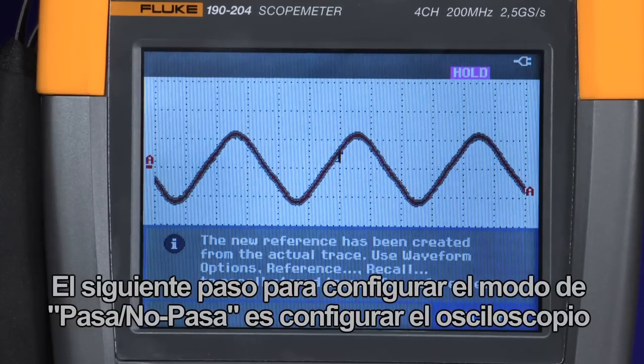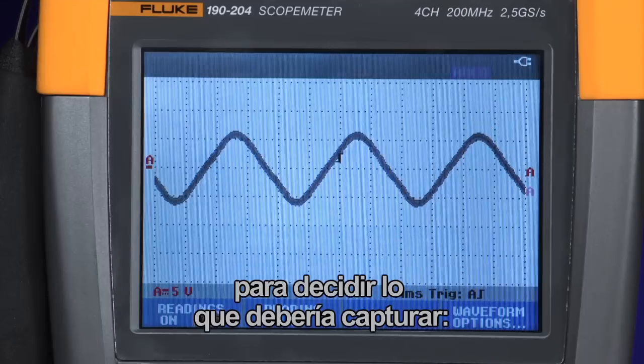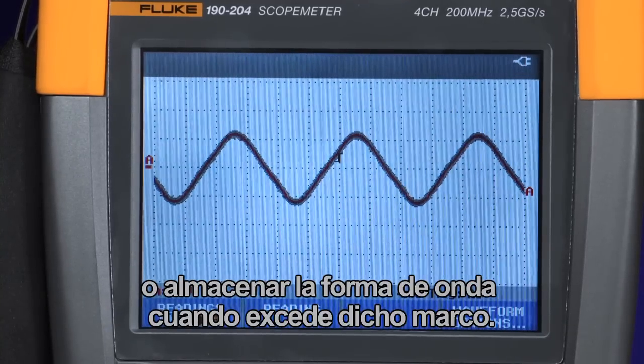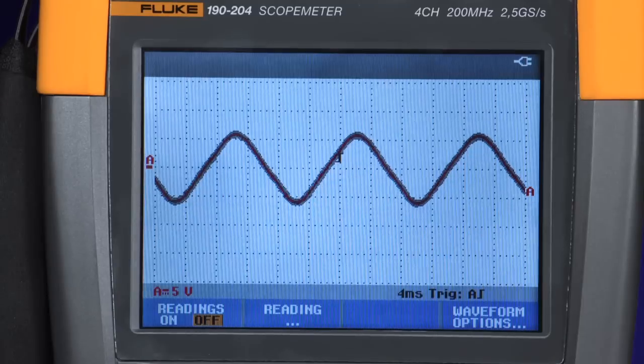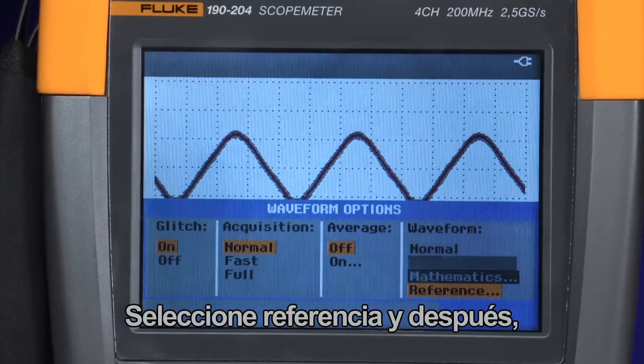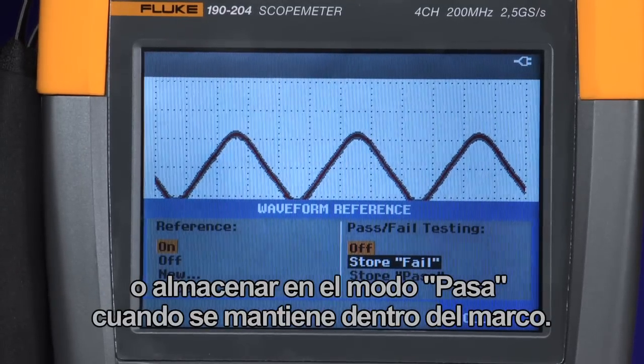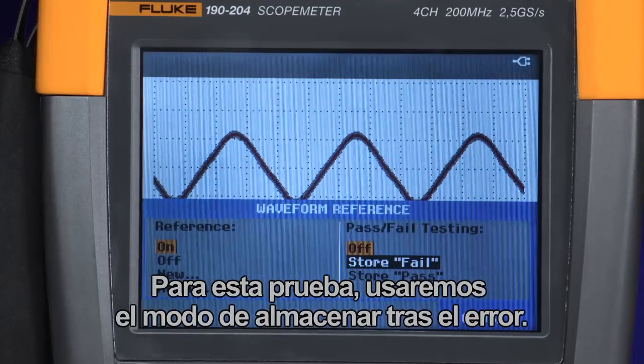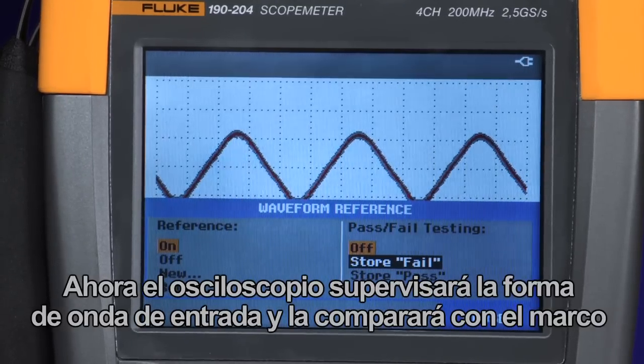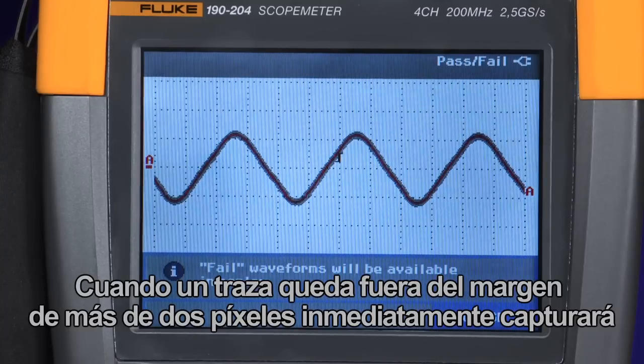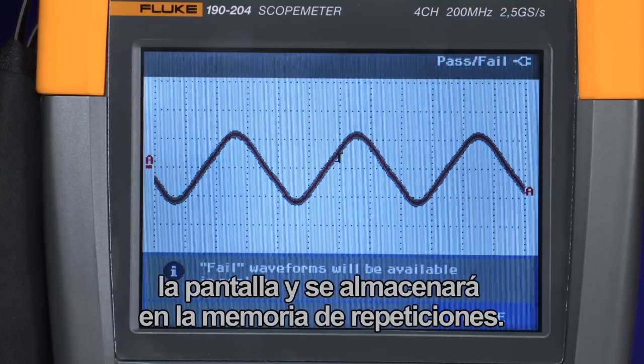The next step in setting up the pass-fail test mode is to set up the oscilloscope to decide what it should capture — whether to store a waveform within the envelope in the pass mode, or store the waveform when it exceeds that envelope. Press the waveform option menu, select reference, and then choose either store on fail when the unknown trace exceeds the envelope, or store on pass when it remains within the envelope.